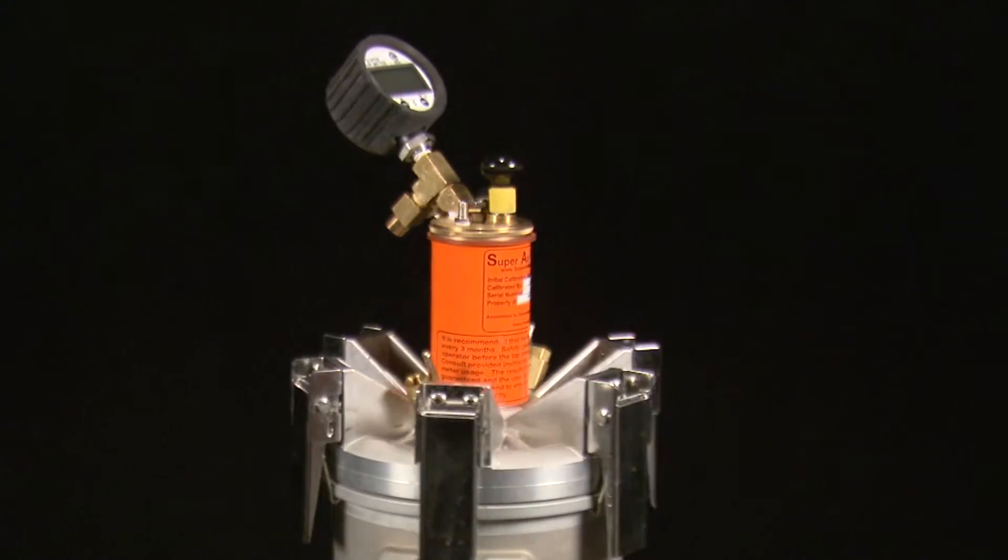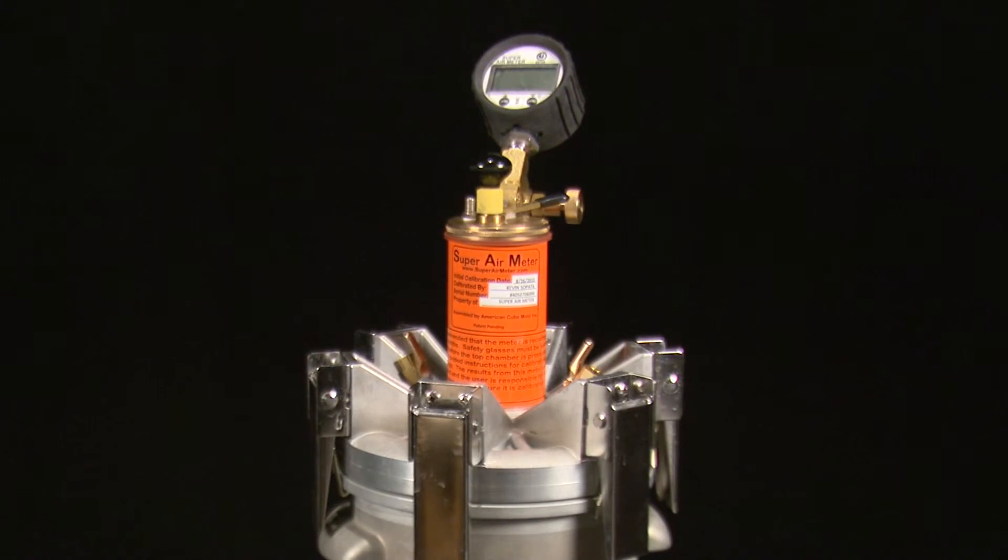After the valve has been changed and you're sure the meter is not leaking, you should recalibrate the super air meter before you perform any tests.